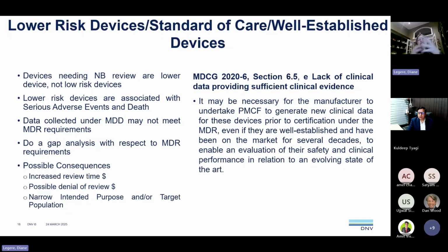It's still a needle and syringe, but it might be made by this manufacturer or that manufacturer, and there's just a little bit of difference in how you had to activate the part of the syringe that would retract the needle. And then nurses were not using it in the way that it was intended. It wasn't retracting appropriately. And it was really just because they had been using this other similar device and were trying to use it in the same way.